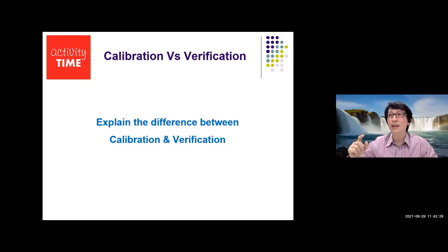Now you go to, let's say, Penang, another factory there. They also recognize this 10.0. So you bring it to India, you bring it to America, China, Russia, Europe, everywhere, it is 10.0 because it is standard. Standard means everyone recognizes and agrees on the same value. All right? So the point is, when you do calibration, you must use a standard. When there's no standard, it is not a calibration. Let me repeat. When you don't use a standard, that is not called calibration. Only when you have a standard, we call it calibration.